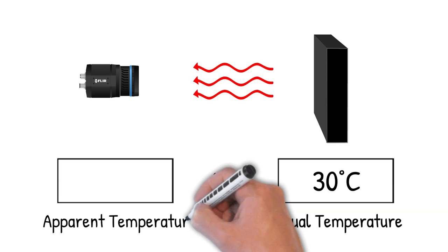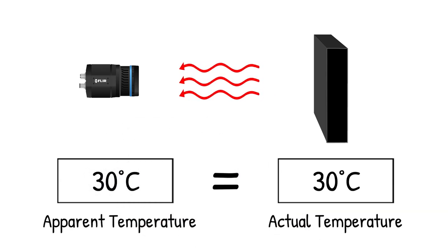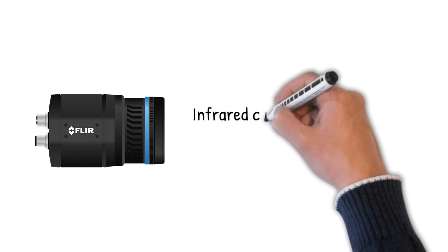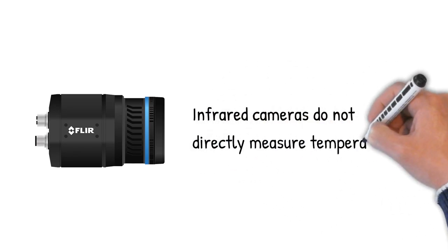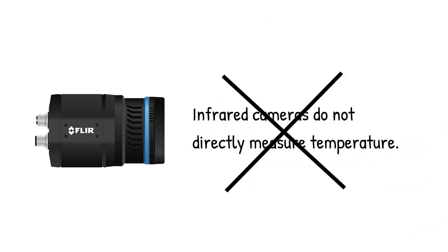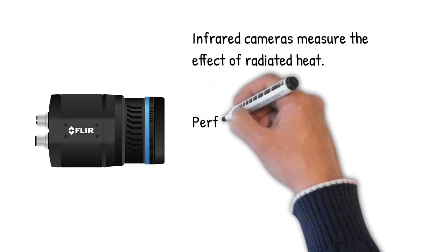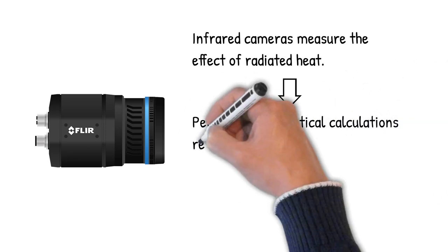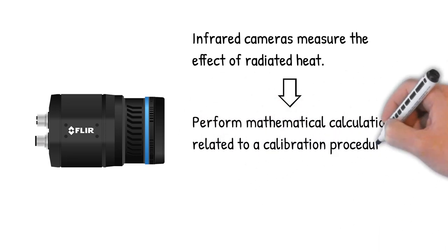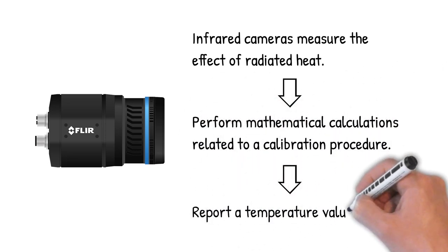The apparent temperature is the temperature value reported by our infrared camera. Infrared cameras do not directly measure temperature. Infrared cameras measure the effect of radiated heat, perform mathematical calculations related to a calibration procedure, and then report a temperature value.